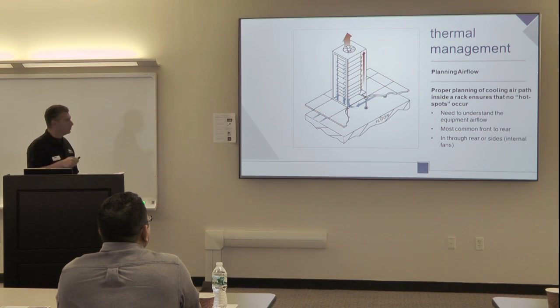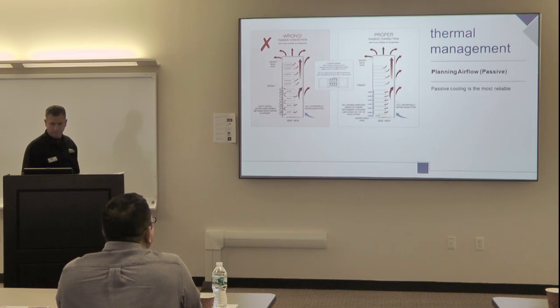So again, the most common is front to rear, which is what we're seeing today. And basically what you want to make sure is you don't create any hot spots. A hot spot is when the hot air gets caught inside the rack, because it may have cool air where it can't get through. You'll see it in a couple of slides with a little graph showing it. So we'll move on to that.